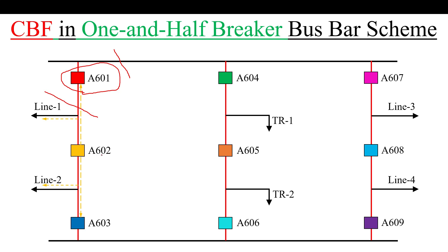If A602 fails to operate, how can it be isolated from both ends? For this purpose the tripping will be extended from the A602 CBF relay to Line 1 via A601, to Line 2, and to A603.